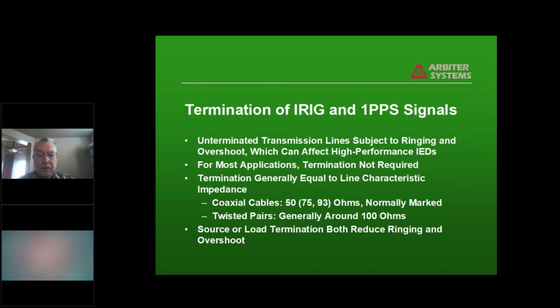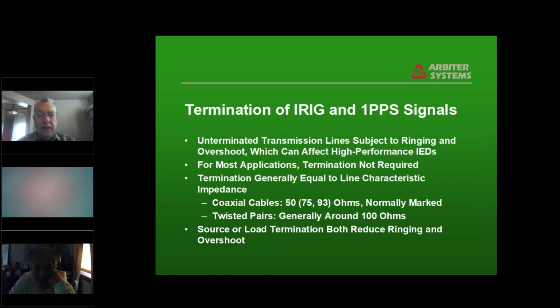As I mentioned, the unterminated lines have ringing and overshoot that will affect high performance IEDs. If you're looking at things down to 50 or 100 nanoseconds with a high speed opto isolator or digital isolator, that device will see that noise and bouncing around on the edges of the signal. So for high performance applications, you need to look at terminating the line one way or another. We'll talk about that in the upcoming slides. For most applications, for recording only, termination usually isn't required. To work properly, termination is usually equal to the line characteristic impedance, which is a matter of the dimensions of the line and the type of dielectric it uses.